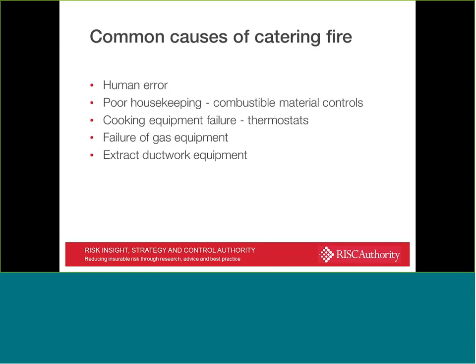Statistics weren't really refined enough to give us any more detail than that, but NFPA information indicates that they have a sufficient number of fires each year in kitchen catering extract ductwork that results in losses in excess of $100 million, again on an annual basis. So it's really quite a significant issue and something that we probably pay too little attention to.